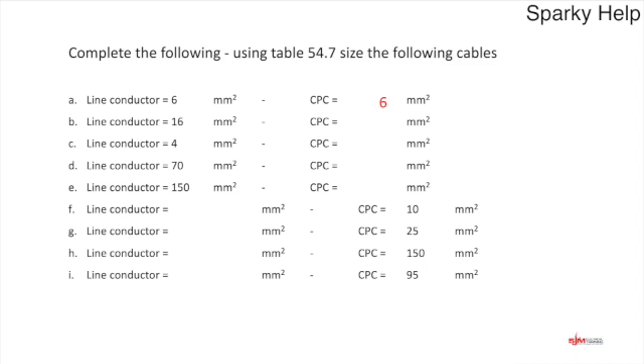If we look at the first one, because it's a 6 mil, the earth that you would put in would also be a 6 mil. And this is all sized to Table 54.7, a bit like a rule of thumb, really. Then 16 mil, well, hopefully you've looked at that, and that would also be a 16 mil. 4 mil, if your line conductor is a 4 mil, remember your neutrals will probably also be the same size, there would also be a 4. For a 70, well, that becomes a 35. For a 150, well, half of 150 is 75, but they don't make a 75, but the next cable up is a 95.